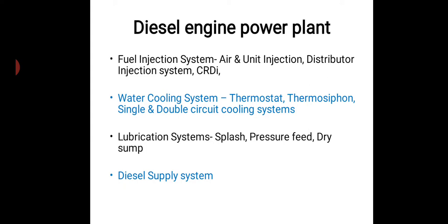Whereas in the case of steam power plant and all, it is more. It takes hours together to start a steam power plant, because so many equipments are there, and to commission that it takes time. But DG set can be started even within a minute, and sometimes some people keep it in auto start position, so that once the main power gets tripped, the DG power starts immediately.